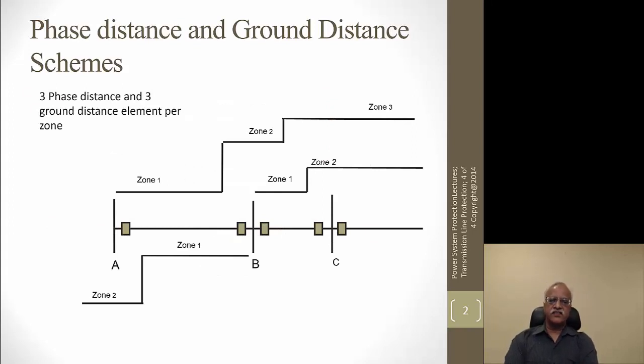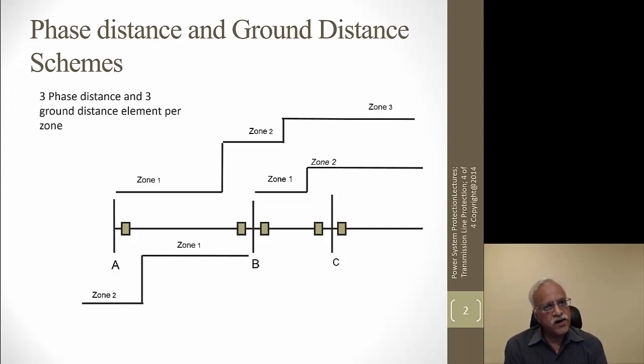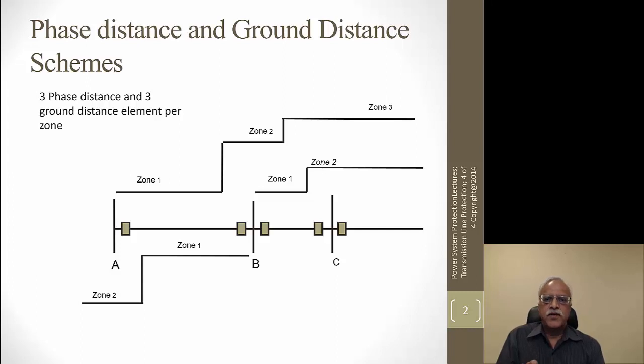We covered in the last lecture how we set the distance elements. There are three elements inside the relay to detect three types of ground faults, and three elements which detect three types of phase-to-phase faults, and these also detect phase-to-phase-to-ground and three-phase faults. The difference between these elements is what voltage and current inputs are used. The A-phase-to-ground element uses the faulted A-phase voltage and the faulted current Ia plus a percentage K0 times the neutral current — the ground current.